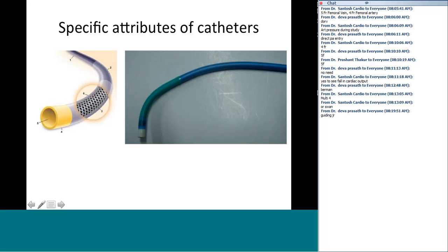Yes, absolutely right, it's a guiding catheter - a right coronary guiding catheter, 5 French. This is a very important catheter, because when you do, let's say, a BPV, or in a situation with pulmonary atresia with intact ventricular septum, it's sometimes very useful to have a guiding catheter, because it will allow a balloon to go through it, and all the coronary work is done through the guiding catheter. You can see this portion is reinforced, so that whatever torque you give at the groin is transmitted without fail to the tip. Then there's progressive softening, less reinforcement, and at the tip there's no reinforcement, so the tip is atraumatic. This is a very important aspect of catheter design.